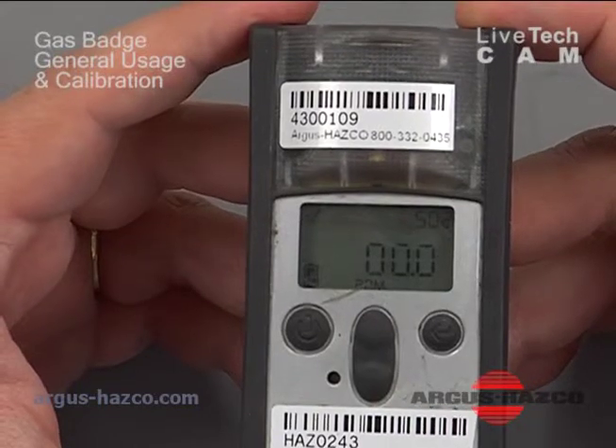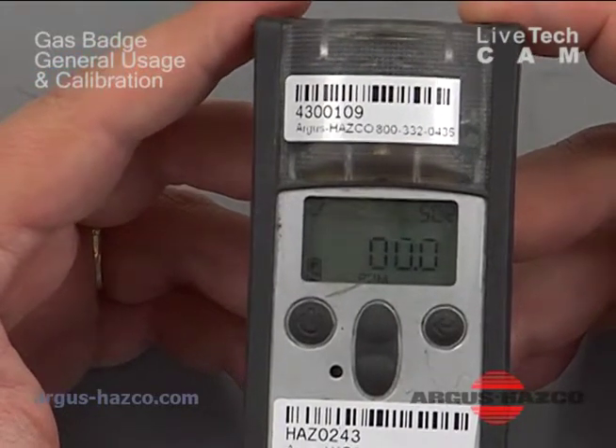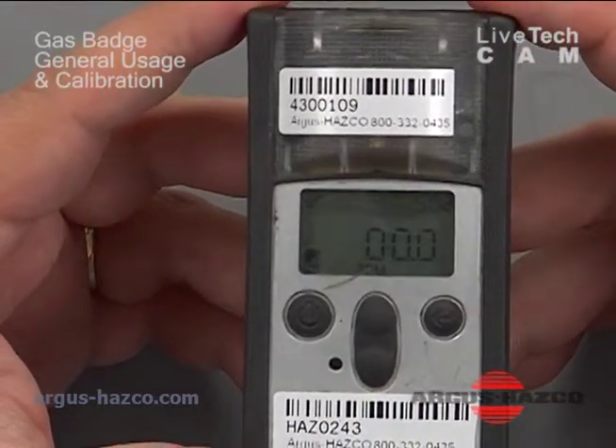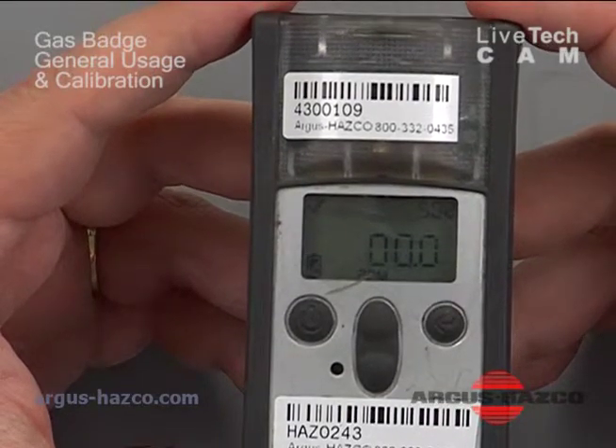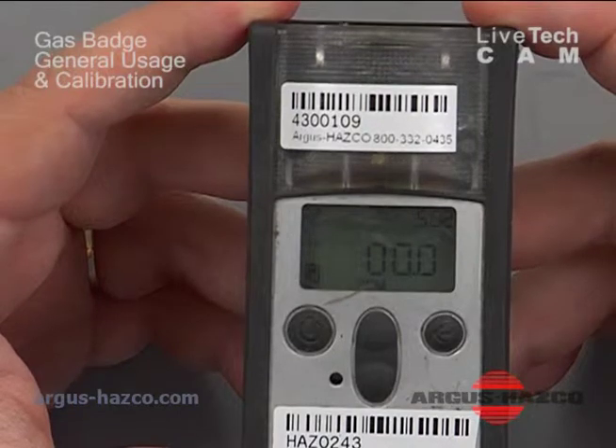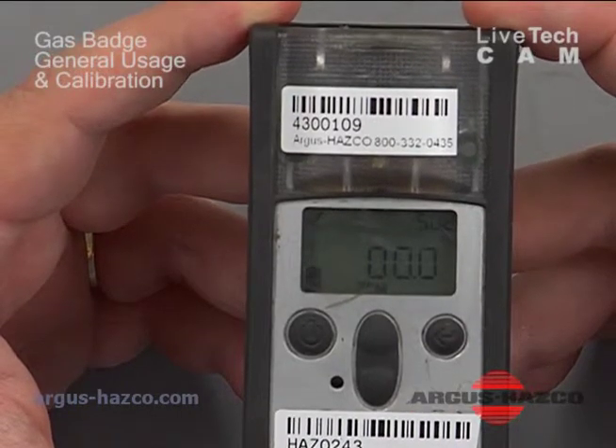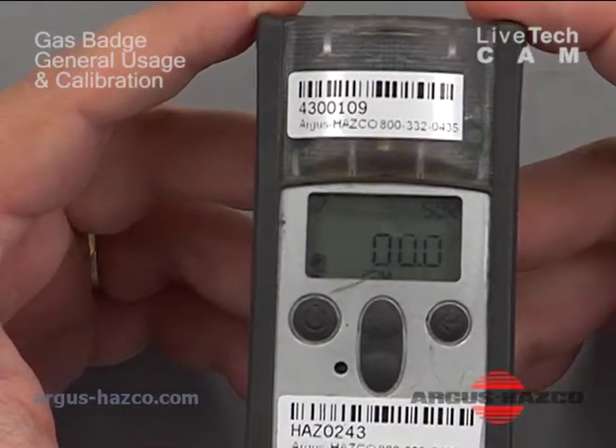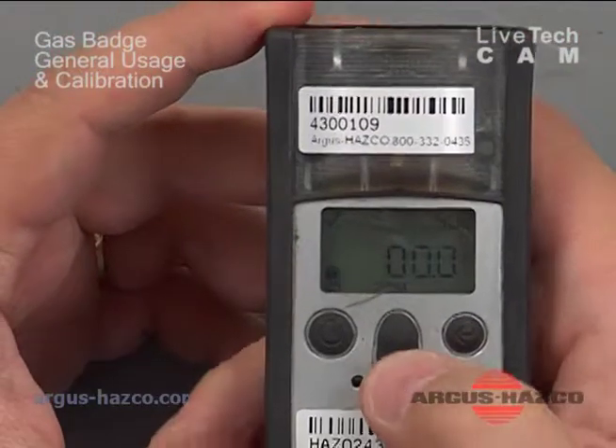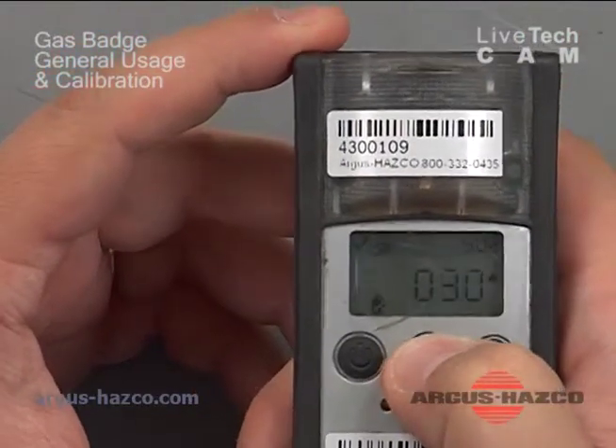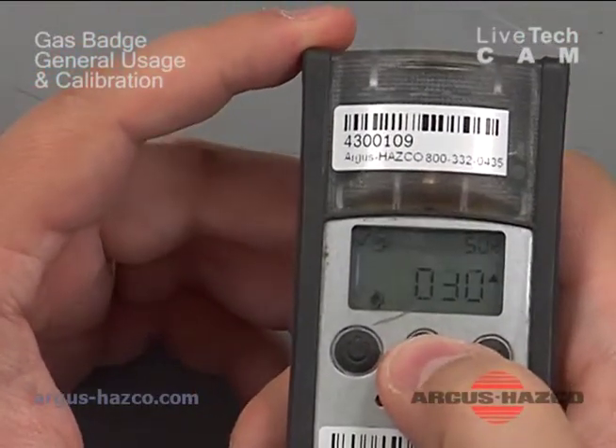And there, it's giving you the direct reading, it's ready to detect. What you're unsure of is if it's within calibration. It showed 30 days until the next calibration, but at this point you may have questioned that. It may have been involved in something and you want to ensure the calibration, so we're going to put it through a calibration. So you can toggle through by using your up arrow. And there again, it's telling you 30 days till its next calibration.